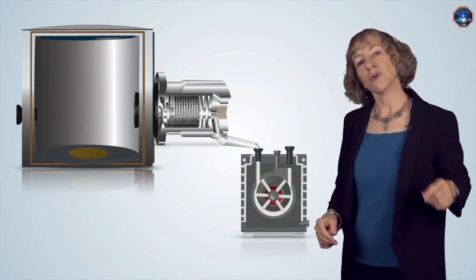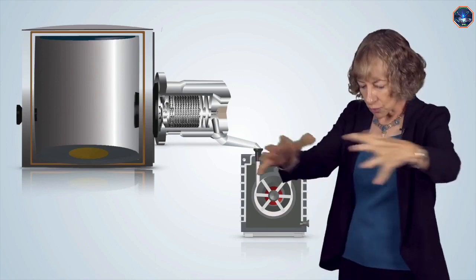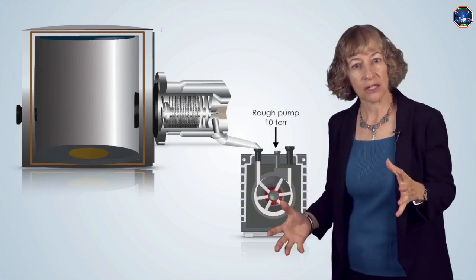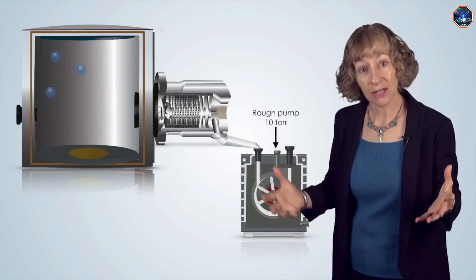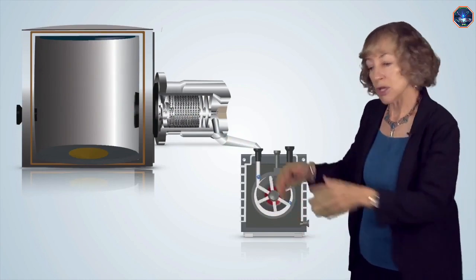So we are going to use the mechanical pump in two different ways. First, to rough out the vacuum system from atmospheric pressure to about 10 torr so that we can turn on the turbo pump afterwards. Second, we use that mechanical pump to back the turbo pump.